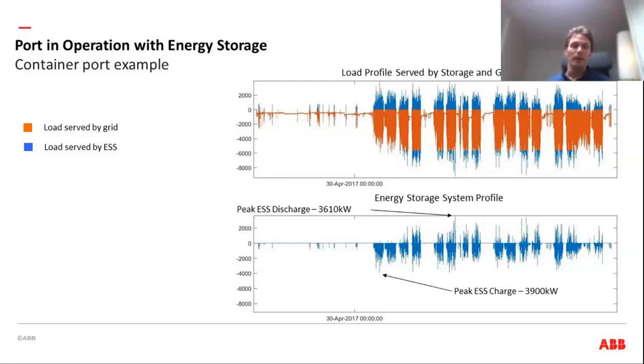And the peaks that we see here are up to 3.6 megawatt. That is regenerative power coming from the cranes. And then we also have very large demand peaks of approximately 9 megawatt hour. So in order to address this, if an energy storage system is considered, then it would provide peak shaving to manage this and to reduce the demand charge levels by a lot. So the idea is that when the battery is integrated, the orange segment here is addressed directly by the grid connection, while what you see in blue is managed by the energy storage system.